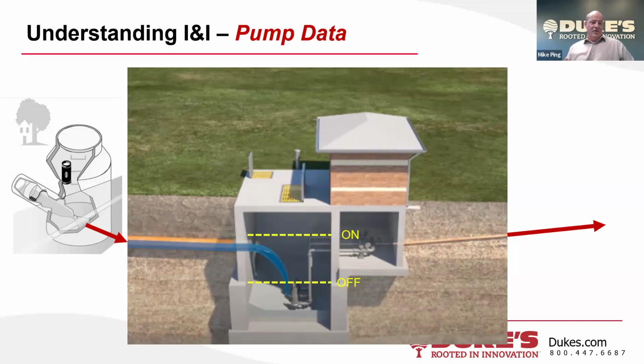Then the pumps turn on, and you get a situation where the flow meter is recording flow that's moving fast, and then the pumps turn off and it's filling up, and the velocity is very low, and it may go all the way to where the velocity is zero. If there are multiple pipes coming into a wet well, the velocity could theoretically go negative.